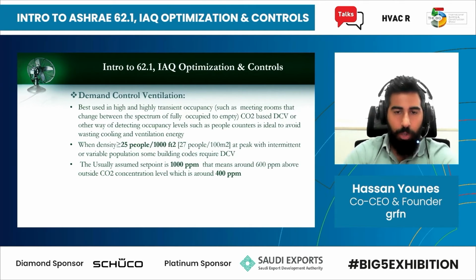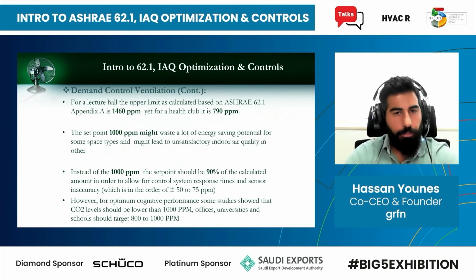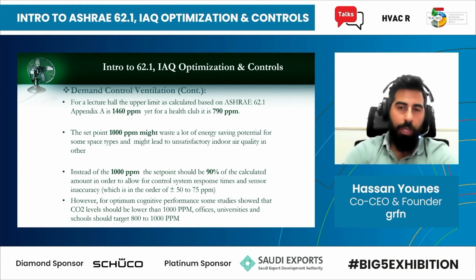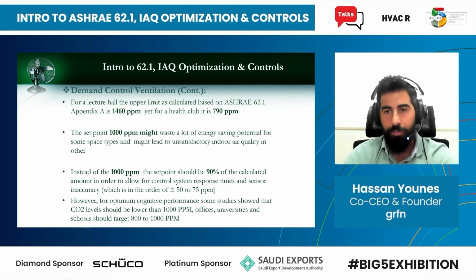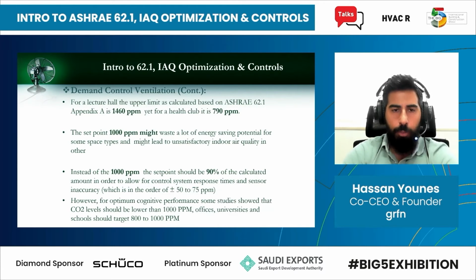The usual set point is 1,000 ppm, and that's normally for an office building, which is around 600 ppm above the outdoor concentration. However, if you look at the different occupancies, even if you apply the standard 62.1 requirements in terms of the amount of outside air, you might end up with a ppm of 1,460 in some of the occupancies. Like if you go to the movies, let's say, in the cinema. In the cinema, you might have high ppm because you have a lot of people, even if you supply the required outside air.